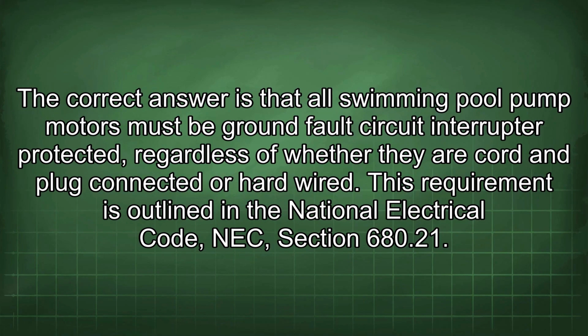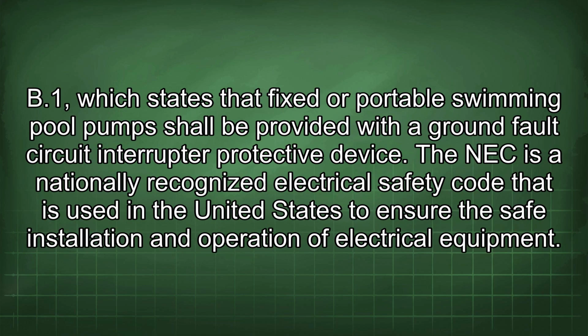The correct answer is that all swimming pool pump motors must be ground fault circuit interrupter protected, regardless of whether they are cord and plug connected or hardwired. This requirement is outlined in the National Electrical Code, NEC, section 680.21(B)(1), which states that fixed or portable swimming pool pumps shall be provided with a ground fault circuit interrupter protective device.